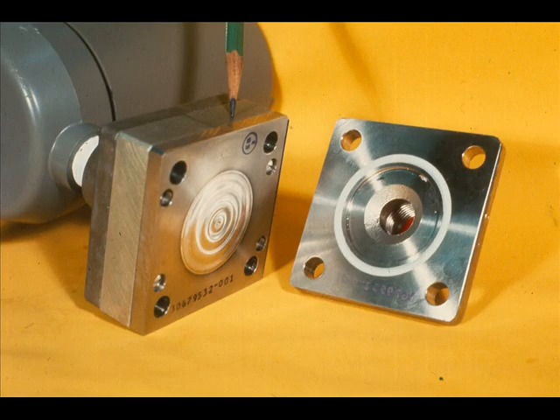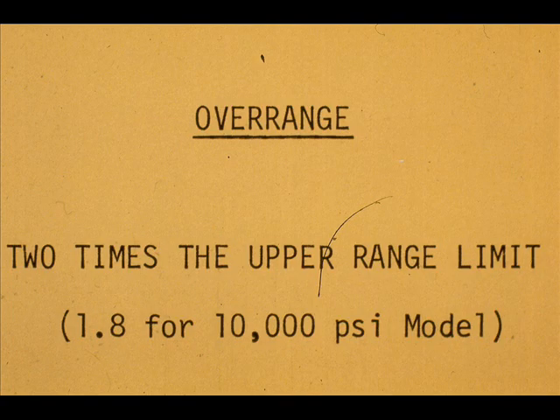The pressure range is determined by the selected body assembly. The over range limit is twice the upper range limit for a given body assembly.